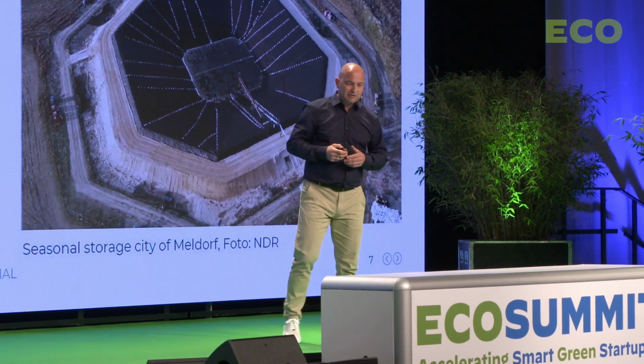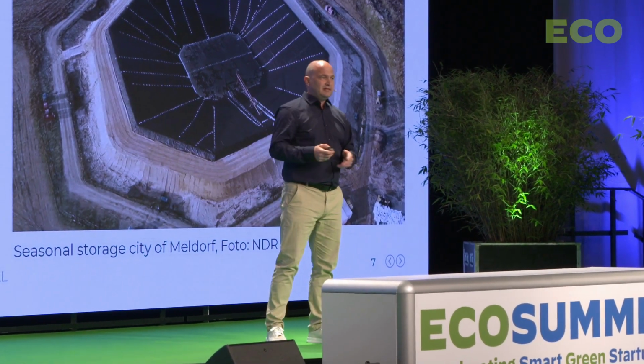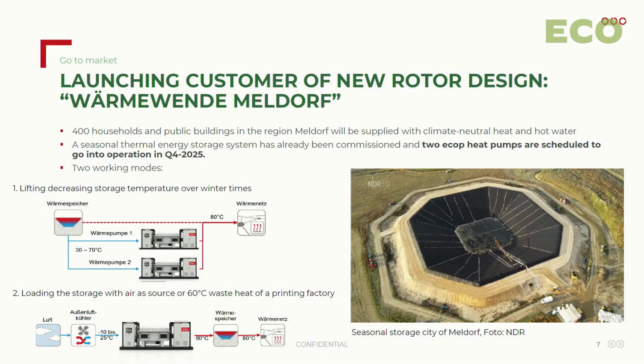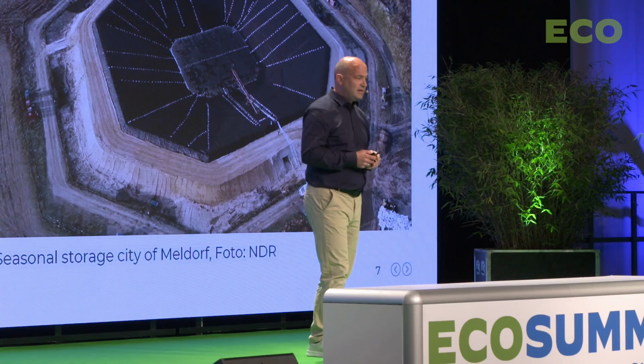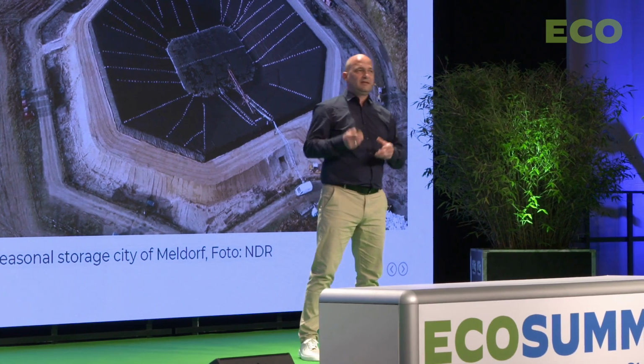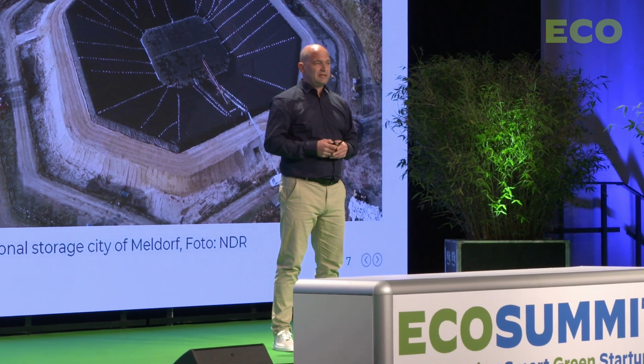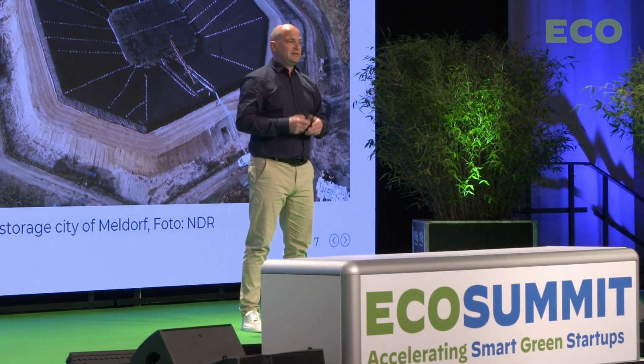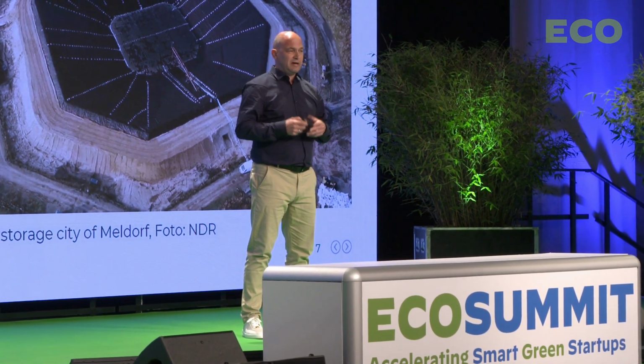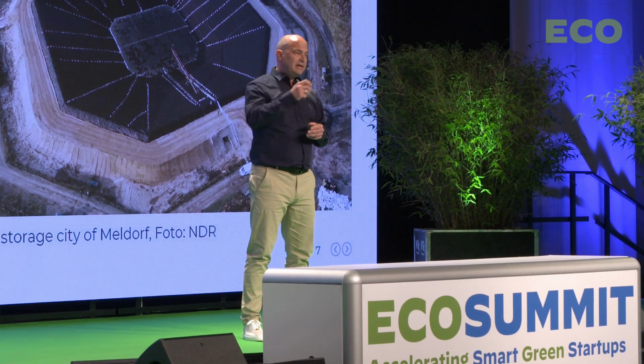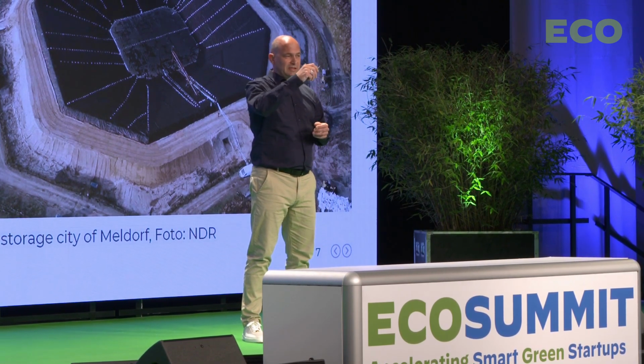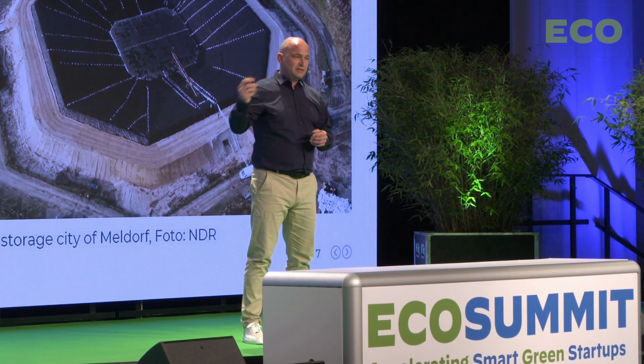So how does this translate into use cases? Here's one example: the first commercial project with our new rotor design, where we connect two heat pumps with a seasonal storage — a water basin, the first one in Germany — where the heat pump lifts the waste heat of a printing factory at 60 degrees C up to the 90 degrees C required for the storage. Over the winter, it pumps from the decreasing temperature of the storage into the district heating grid.